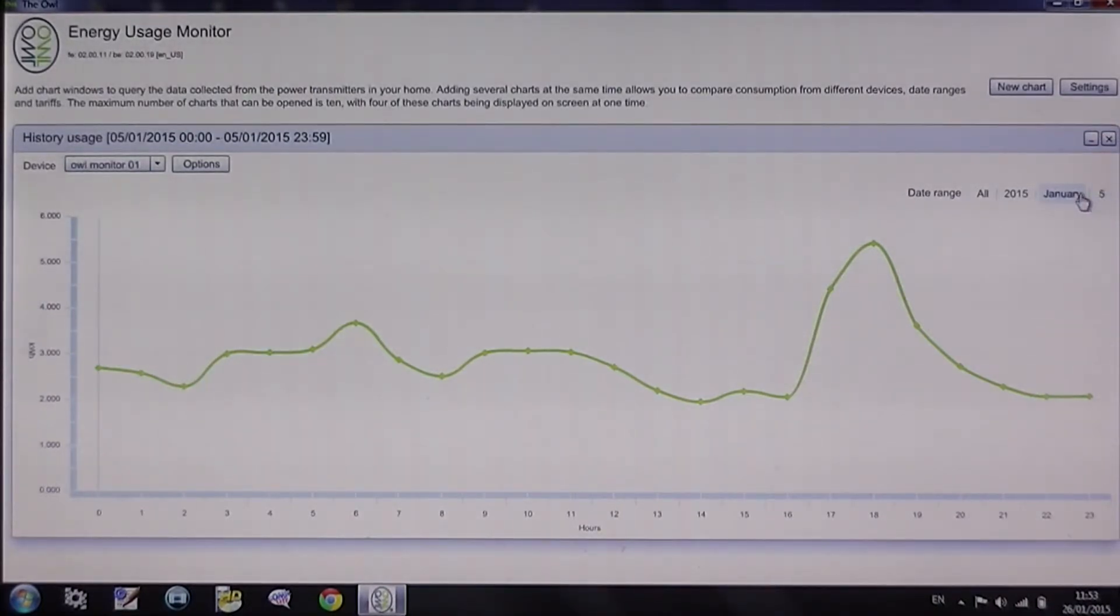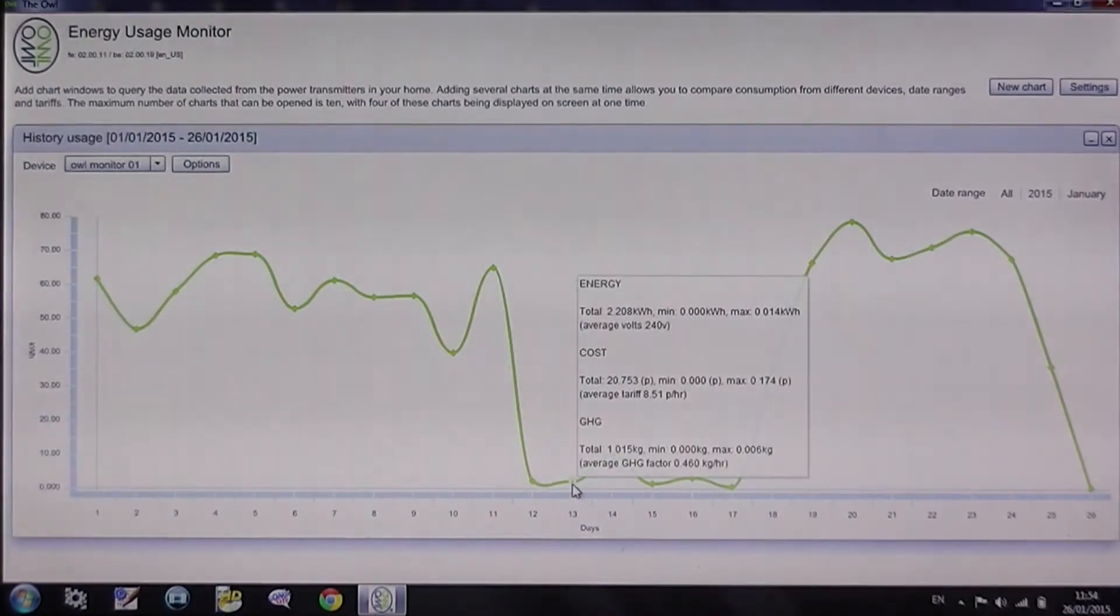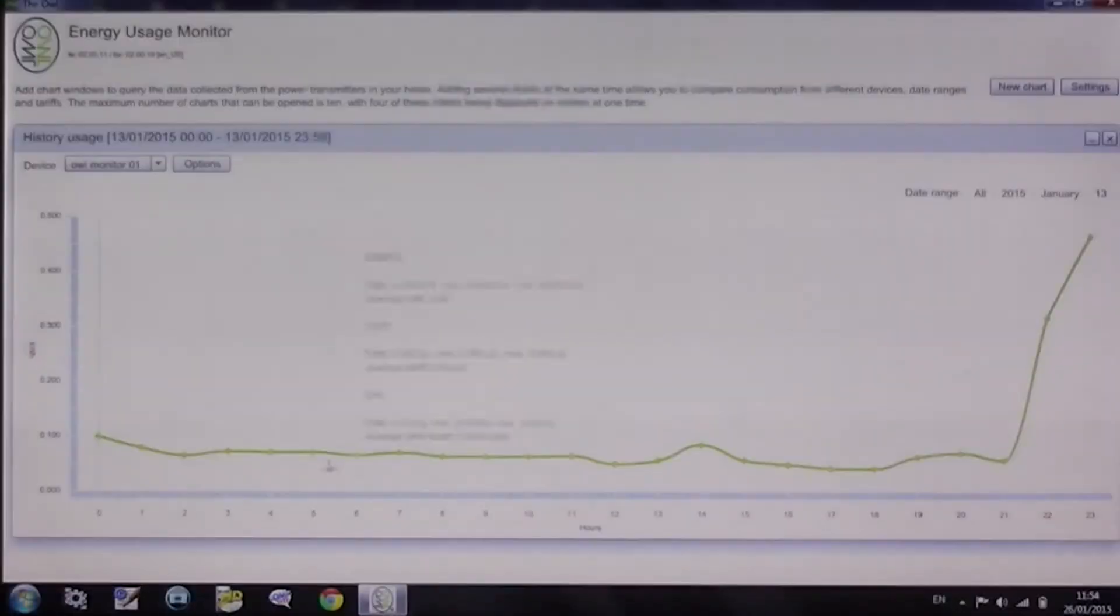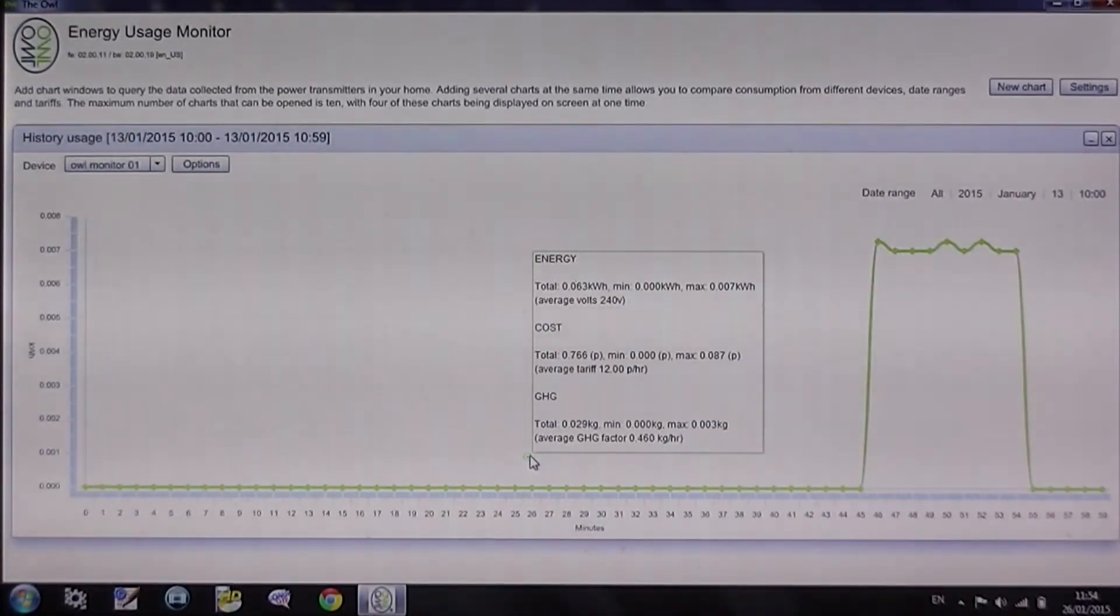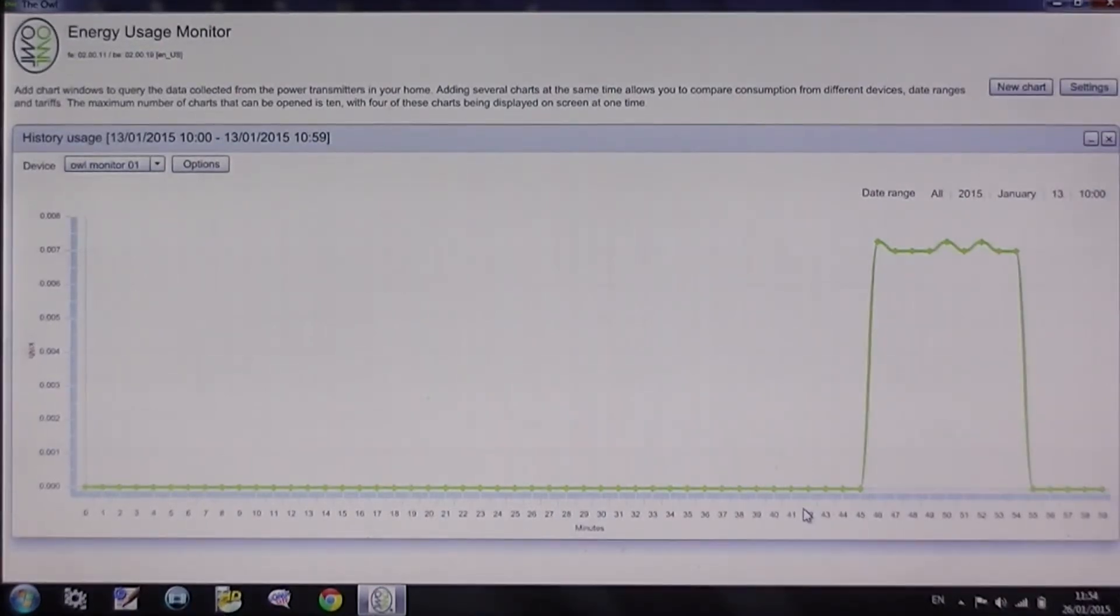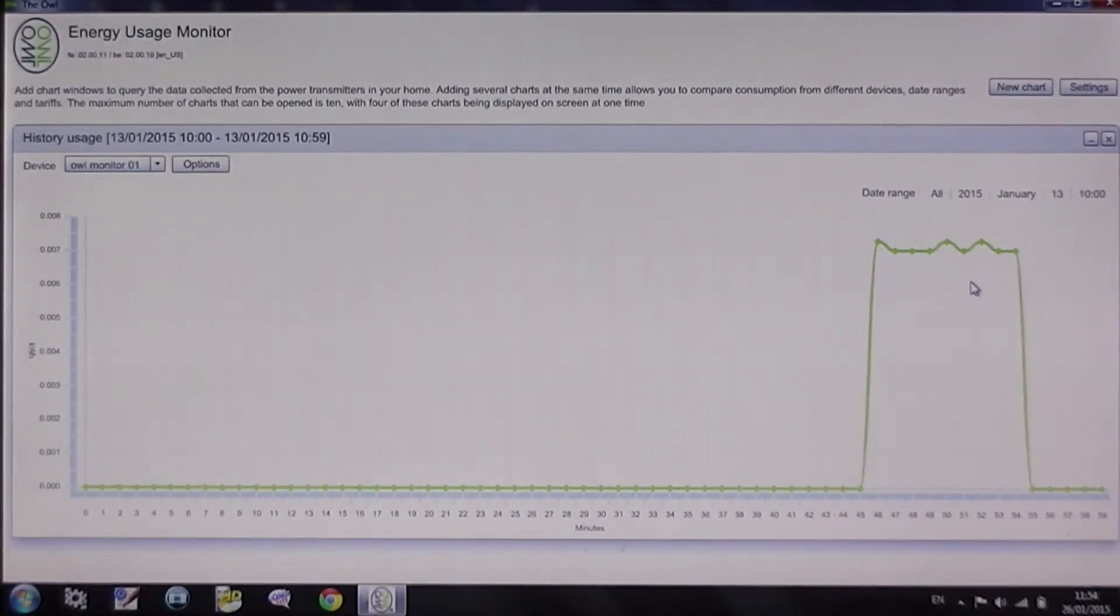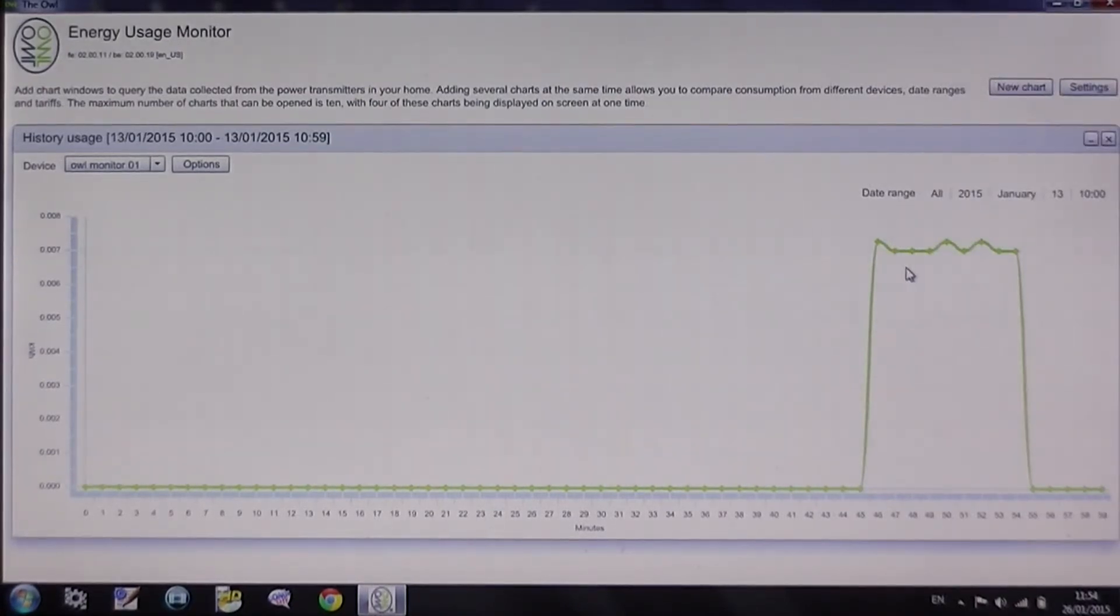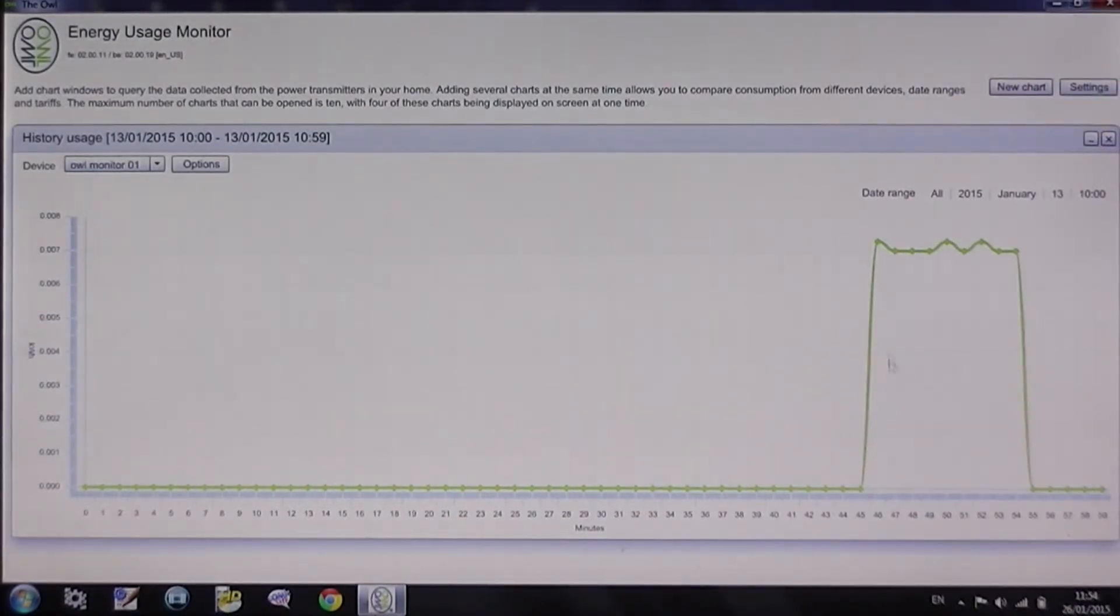Now go back to January. Let's try this one which is the 13th. This is a single appliance test and what we're seeing here is a panel heater, one panel heater. And this is the on period here. You'll see slight variations in the on period because of line voltage variations within the house, perhaps another heater turned on or off, which explains the variation here. This is off completely, that's on.